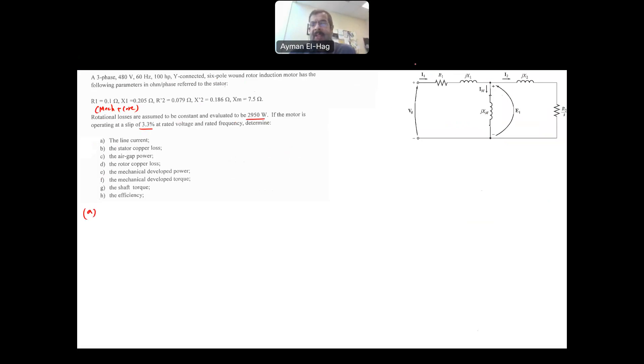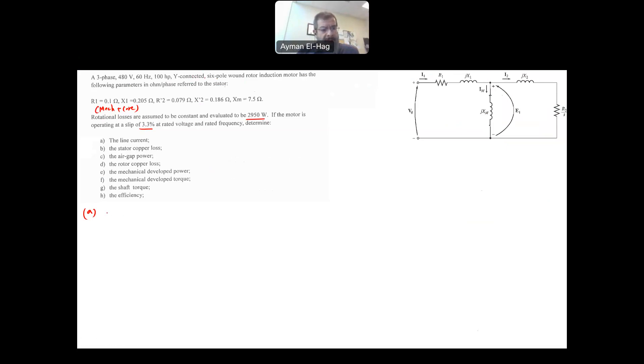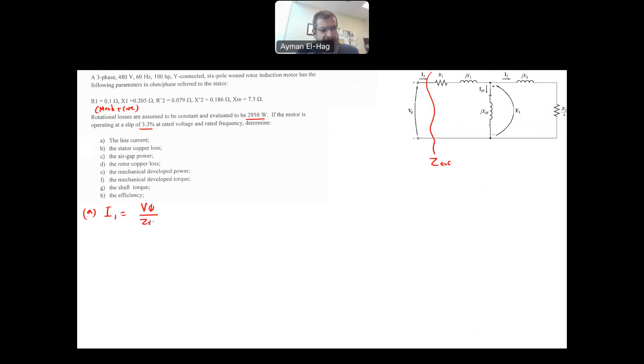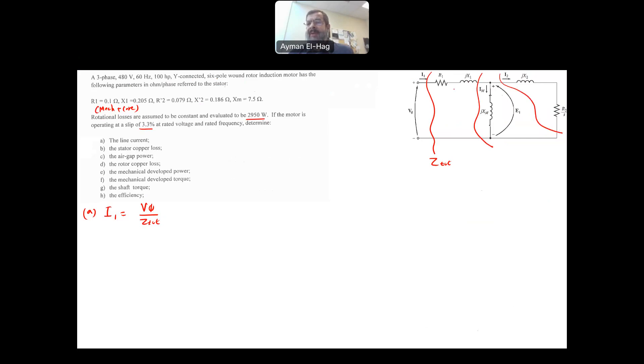The line current is the current supplying the stator. Because it's a Y connection, the line current and the phase current are exactly the same. So I1 is the phase voltage divided by the total impedance Z total. This Z total is basically R2 over S and jX2 in series, in parallel with jXM, and everything is in series with the stator impedance. Let's calculate one by one.